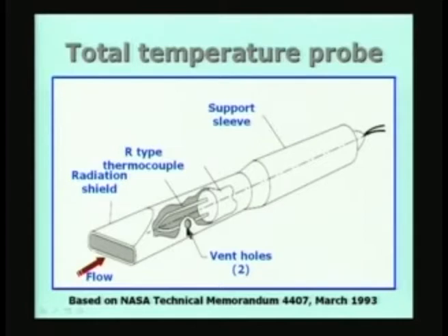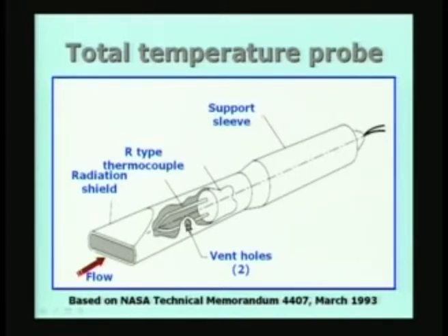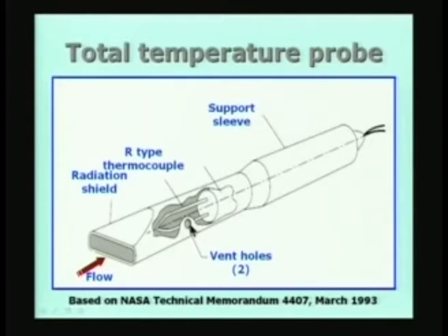Vent holes are provided on the side — two of them, one on each side 180 degrees apart. The flow enters the duct arrangement and comes to stagnation near the probe, then moves slowly out through the vent holes. The area ratio of the two vent holes to the inlet area is about 0.5 to 0.6, found to be the most desirable ratio. This means the vent holes are smaller than the inlet cross section.